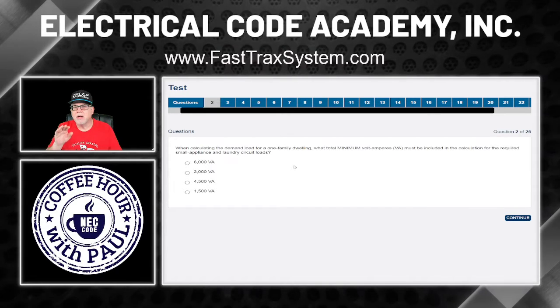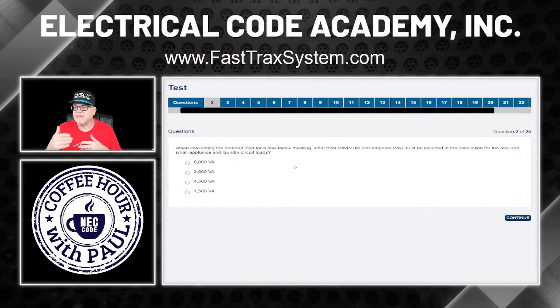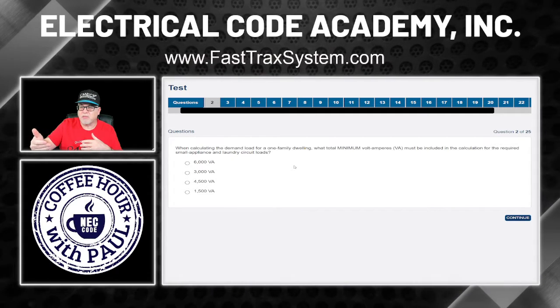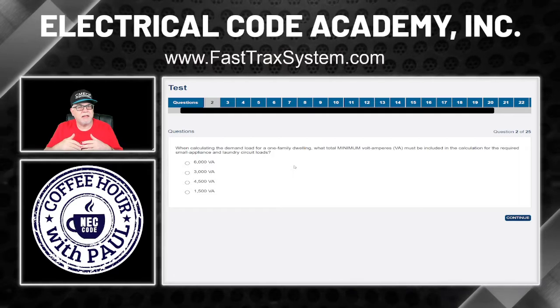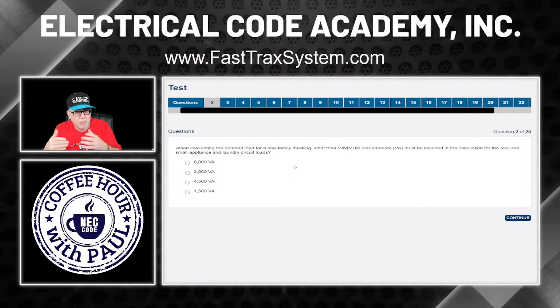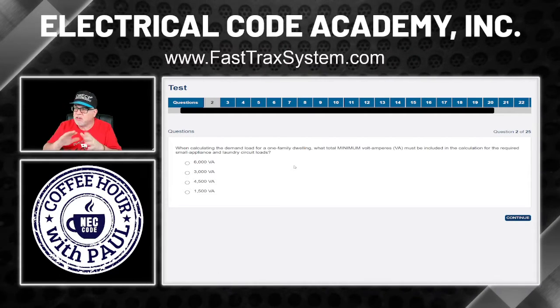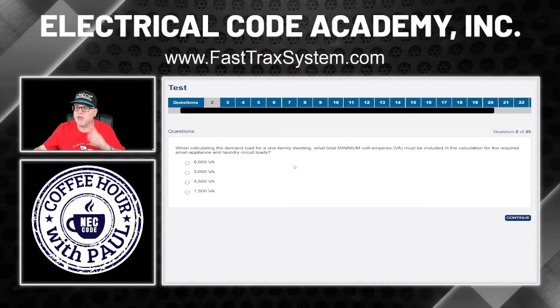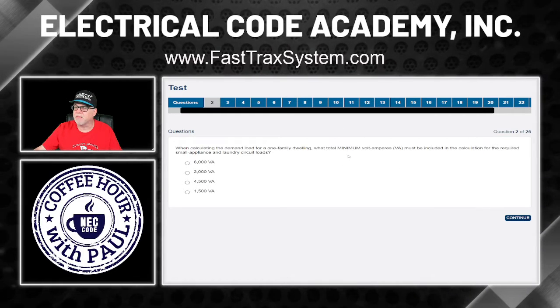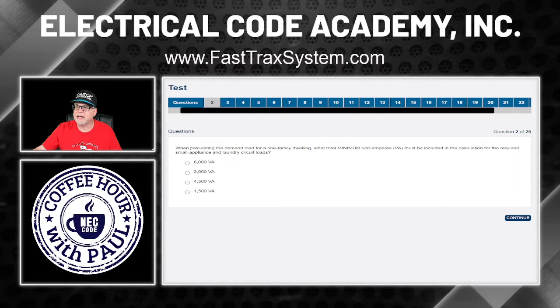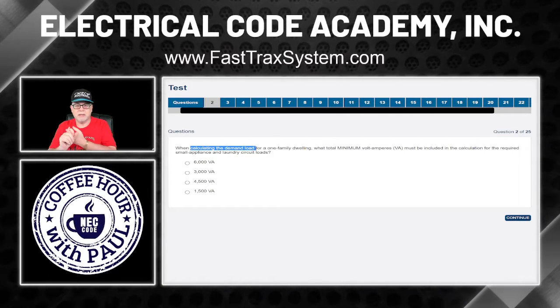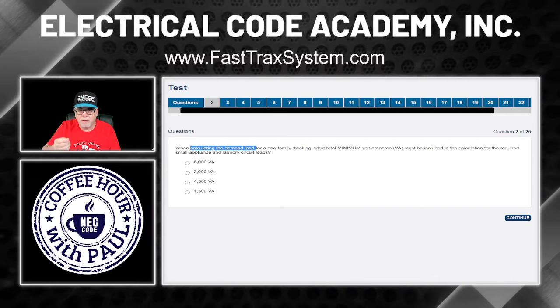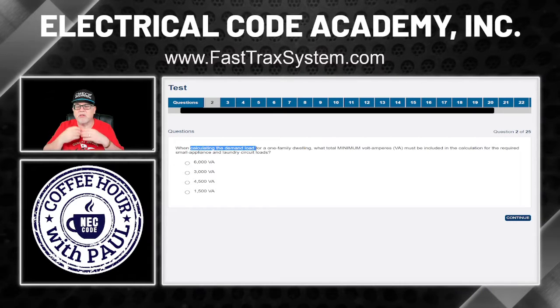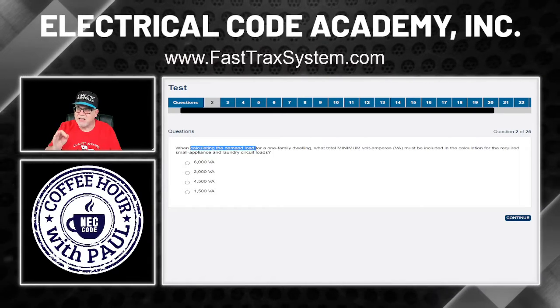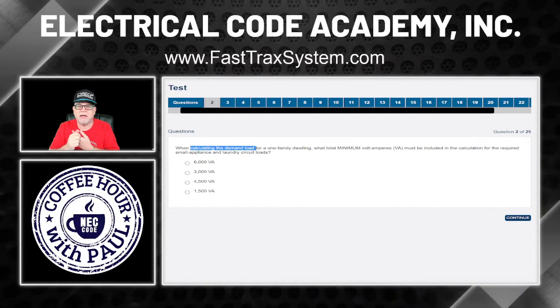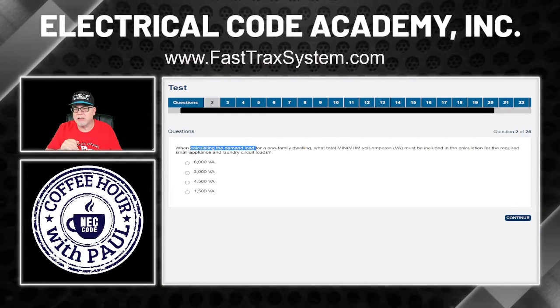Calcs. Now, if your question is about the branch circuits themselves for these small appliance and laundry circuits, then that would be 210, right? Because that's branch circuits. They didn't mention anything in here about the branch circuits. So the most important takeaway here is that it wanted to calculate the demand load. There's a load involved in this, so it wants you to know that. When I see that load and there was no mention about a branch circuit or anything like that, then I know that we're going to be looking at 220.